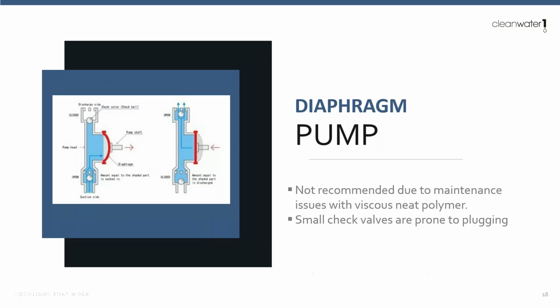And then finally, the diaphragm pump. This is an excellent pump for so many different chemicals and so many different applications. It's just really not the right pump for neat polymer. It's not recommended due to maintenance issues with viscous polymer. They have really small ball type check valves in the inlet and the discharge. And again, neat polymer has a way of finding those little areas and clogging it. And what we've seen just in our thousands and thousands of installations is these can potentially cause maintenance concerns and headaches with the amount of plugging and maintenance required to clean them. So we generally try to stay away from diaphragm pumps for neat polymer applications. Again, it's a great pump for so many different applications. Neat polymer is just not really one of them.